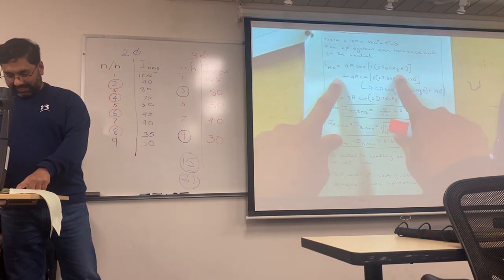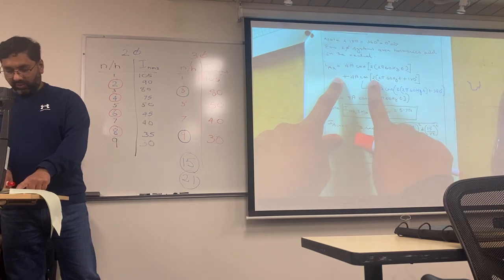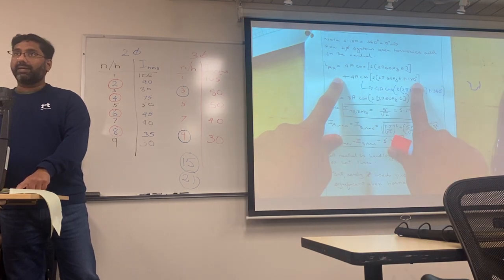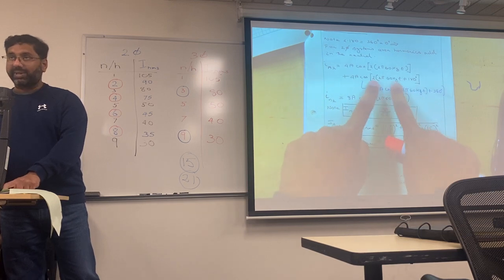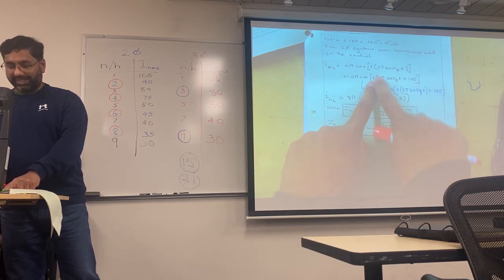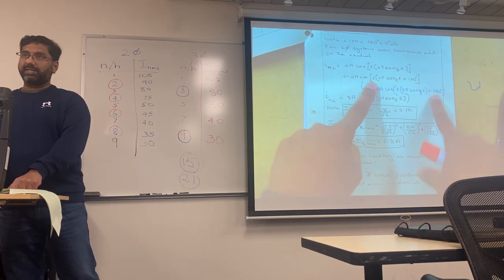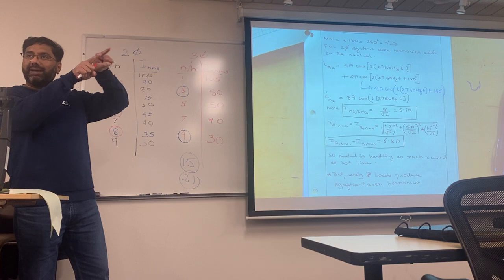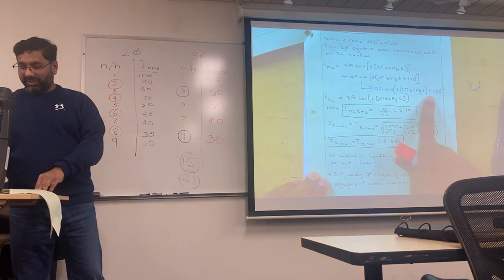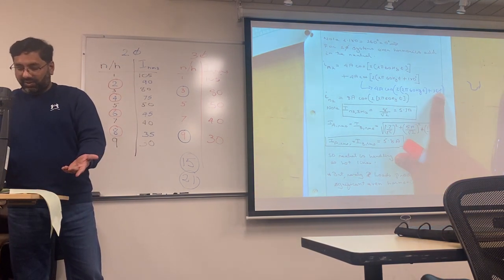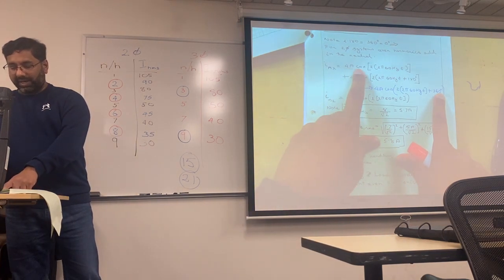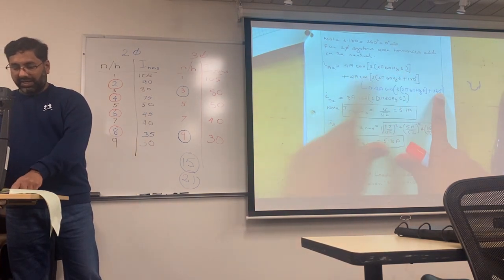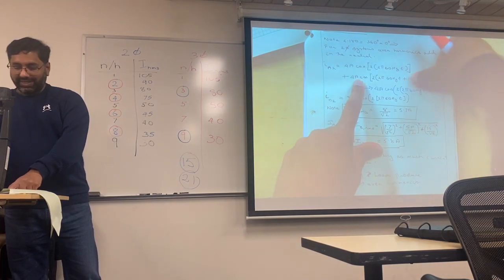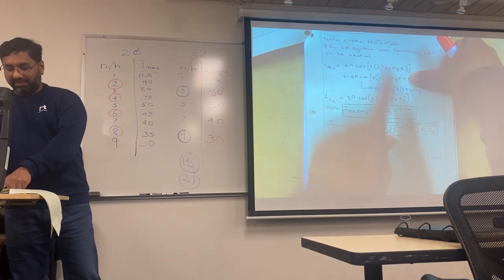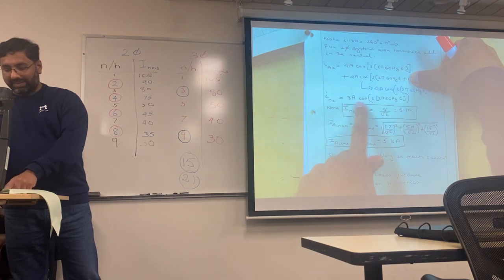What happens in the second harmonic is it's 2 times 180. Can you see that? Because I'm trying to get 120 hertz here. So it's 2 times 60, which is your 120 hertz, and it's 2 times 180, which is essentially 360. So I have 2 currents going in the same direction, because it's 360, it is as good as adding a 0. So I end up with 4A cosine plus 4A cosine, and this 180 doesn't do anything. It's literally the same current. And I end up with 8A.